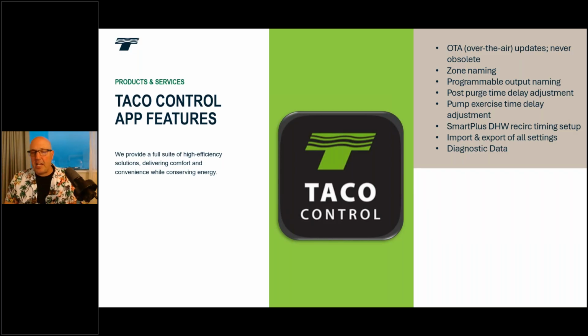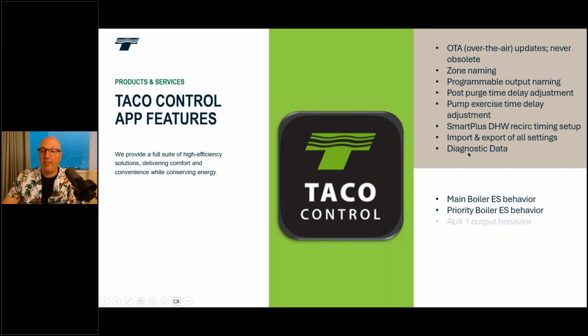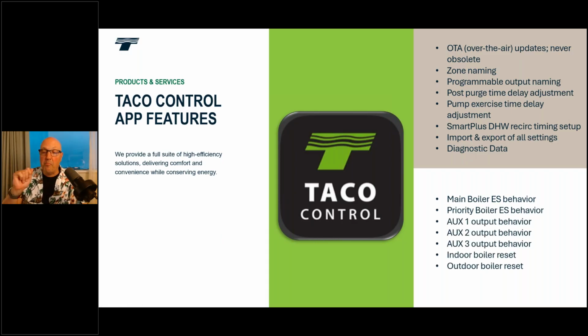And that's all nice and neat. But then we also have that post purge. The default is 2 minutes. I can change that runtime up to 5 minutes if I wanted to, or bring it all the way down to 30 seconds. Your low mass boilers, let's take a little bit of BTUs, scrub them out of there and put them into the zone. I can change my pump exercise. I can change my Smart Plus options in running. All right. So those are some of the things that we can change in there. Now we can also change the boiler end switch as well as the priority end switch. And I'm going to show you why you would want to control the boiler separately from here. And then we can change my auxiliaries as well. And of course, we can program in the indoor and the outdoor reset from here.